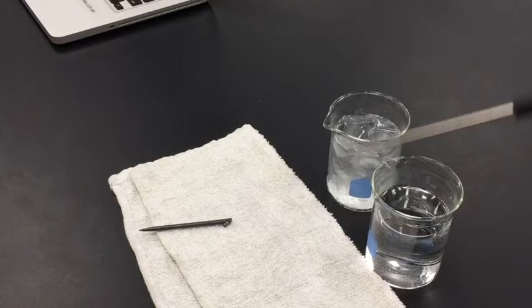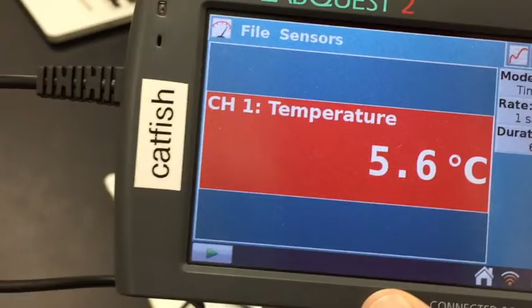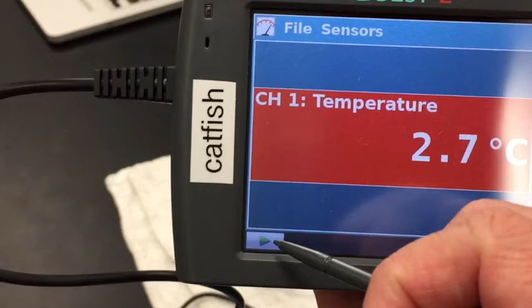First you want the probe to go into the ice water. Right now we're letting it stabilize in Celsius, it's going down to about 5 degrees. We've had some stabilization time, and I'm going to hit start, right down here, this little play button. When you hit that, it means whatever's being read by the sensor is being captured.